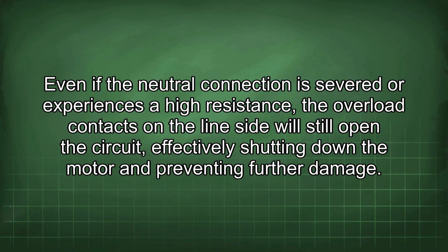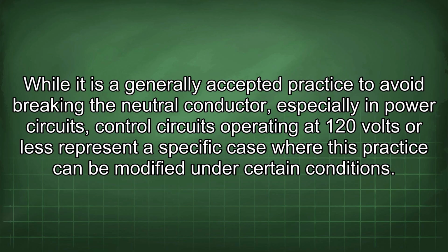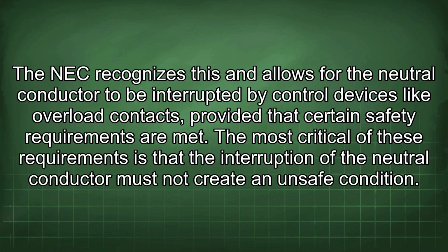Even if the neutral connection is severed or experiences a high resistance, the overload contacts on the line side will still open the circuit, effectively shutting down the motor and preventing further damage. While it is a generally accepted practice to avoid breaking the neutral conductor, especially in power circuits, control circuits operating at 120 volts or less represent the specific case where this practice can be modified under certain conditions. The NEC recognizes this and allows for the neutral conductor to be interrupted by control devices like overload contacts, provided that certain safety requirements are met.